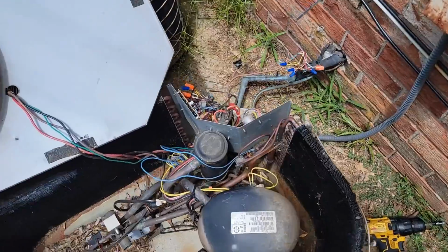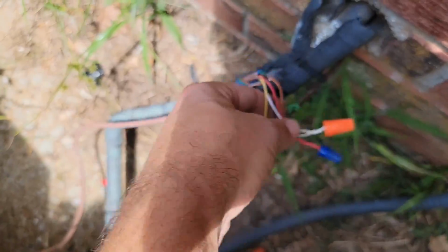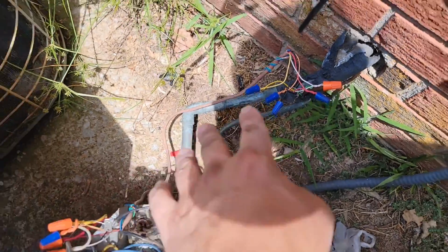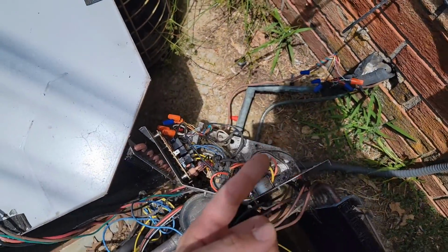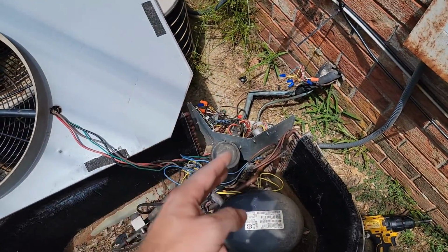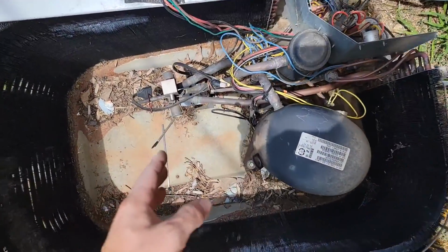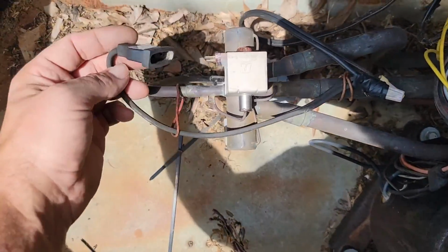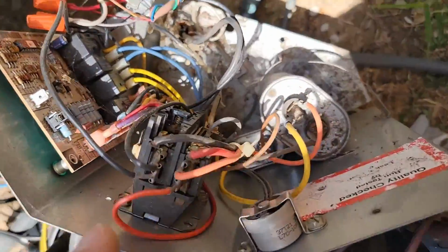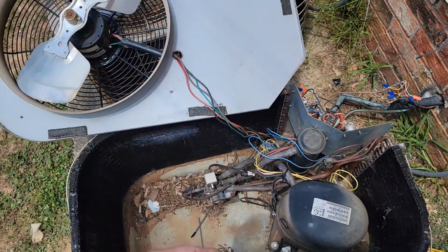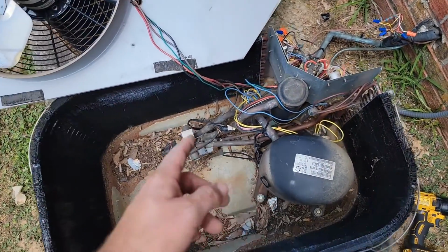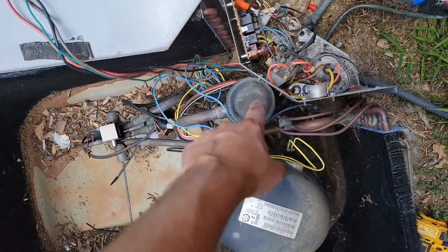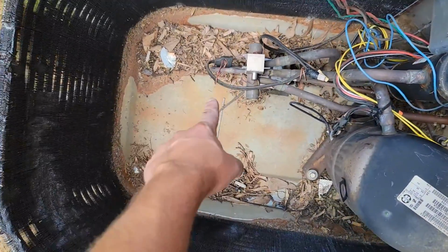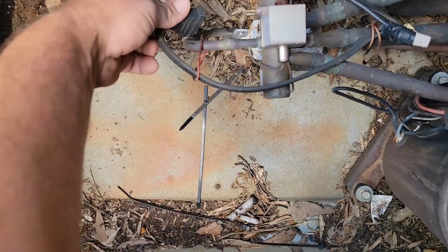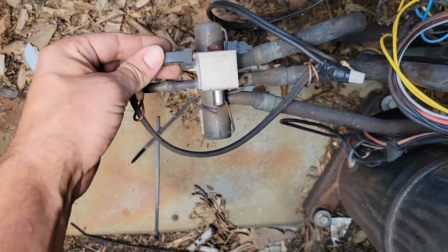Thanks, buddy. Let me show you where I'm at. So I had this bundle of wires. I cut that out. I want to make sure that's not the issue. Went inside, turned the power back on, fuse was blown, okay? Come back out, I take my wire off my reversing valve coil, and I take a wire off my contactor coil. Go back in, turn it back on, fuse doesn't blow. So I know for sure, without a doubt, it's either that contactor coil that's causing the short or that reversing valve coil. So I'm gonna do the reversing valve coil first.